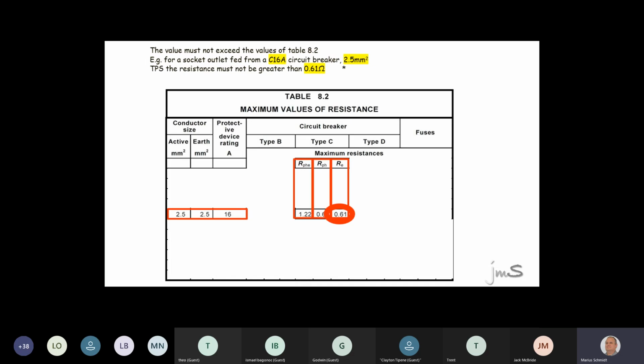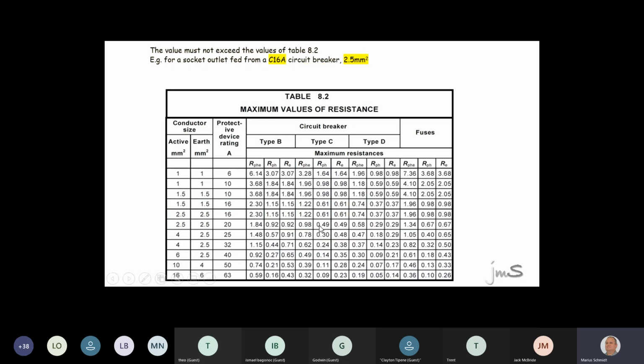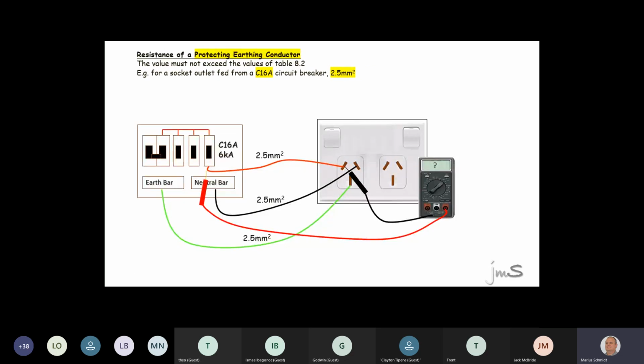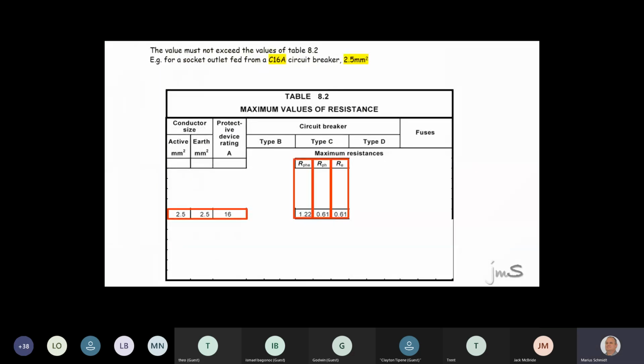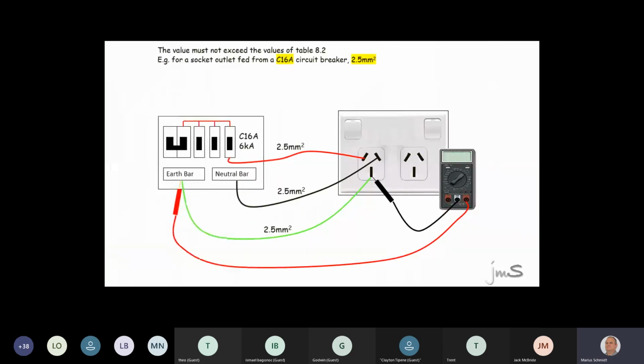Guys, we call this a dead impedance test. Now, can you do this test on a circuit which is with or without a RCD? This test we can do with or without a RCD because we're not live in the installation yet. So you all agree, you can go to every plug circuit, phase and phase, earth and earth, neutral and neutral, and boom, next one, phase and phase, neutral, neutral, earth and earth. Guess what you're doing? You're doing actually an earth loop impedance test as well. Happy with that one? Right, so we call that a dead impedance test.